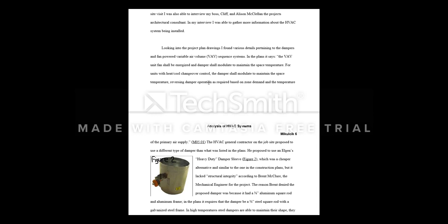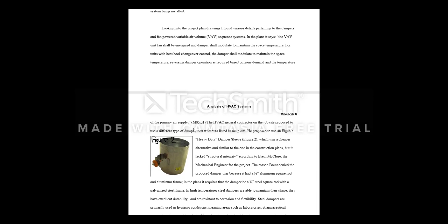Looking into the project plan drawings, I found various details pertaining to the dampers and fan-powered variable air volume sequence systems. In the plans, it says the VAV unit fan shall be energized and dampers shall modulate to maintain the space temperature. For units with heat/cool changeover control, the damper shall modulate to maintain the space temperature, reversing damper operation as required based on zone demand and the temperature of the primary air supply.